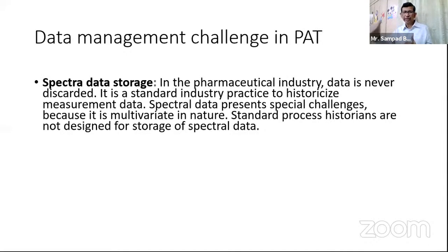When you submit a development report to FDA, if you declare that you have gone through PAT, you have to get your protocol approved, even in development stage, followed by manufacturing stage. That's why all your data, including especially the spectral data, storage arrangement has to be under regulatory compliance and standard. Casually archiving, deleting, or replacing a spectra will not do.